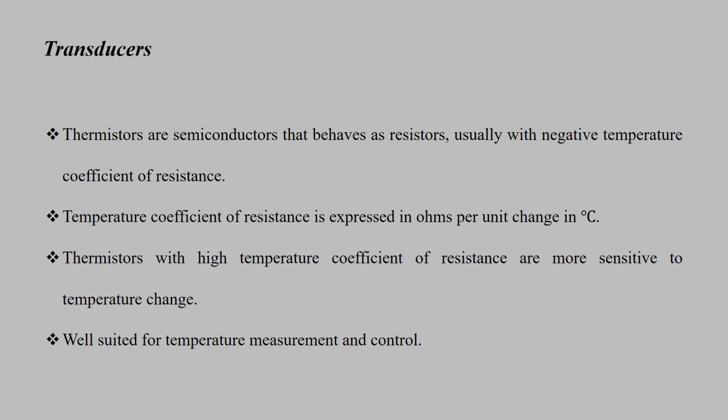The thermistors with high temperature coefficient of resistance are more sensitive to temperature changes. They are well suited for temperature measurements and control. Thermistors are available in a wide variety of shapes and sizes. However, thermistor beads sealed in tips of glass rods are most commonly used because they are relatively easy to mount.